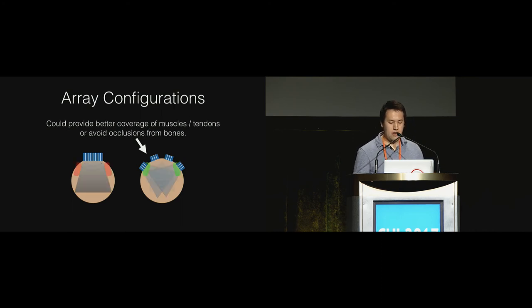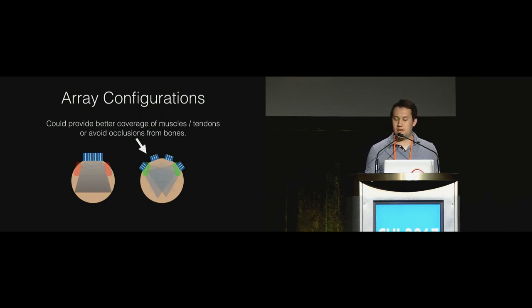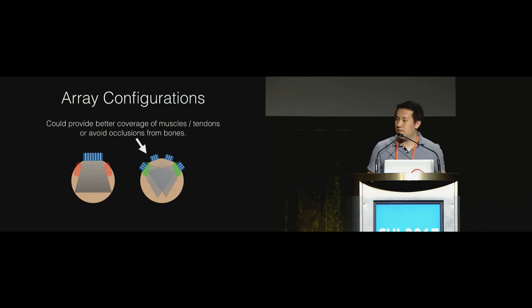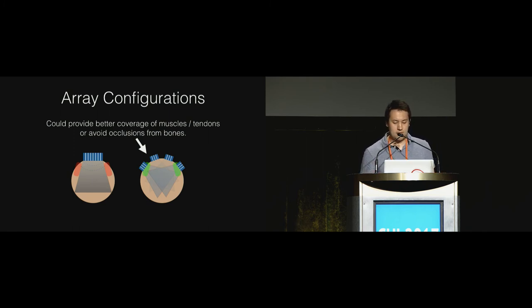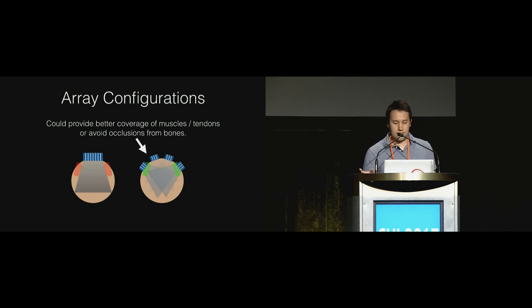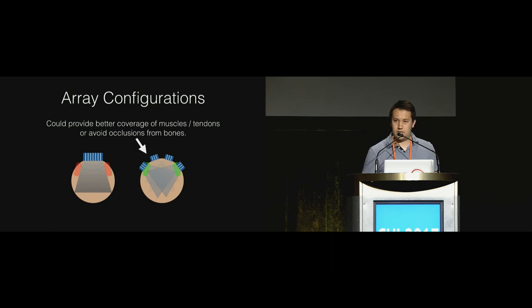Finally, probes are usually designed so that they can scan numerous locations. But if we know where we want to have it, we can place this device statically and design the probes to fit around the geometry of our arms, which may provide better coverage of muscles and tendons. In this image, the linear probe cannot image the bits in red, but these bits can be covered in a different array configuration where it's covering the top part of the arm.